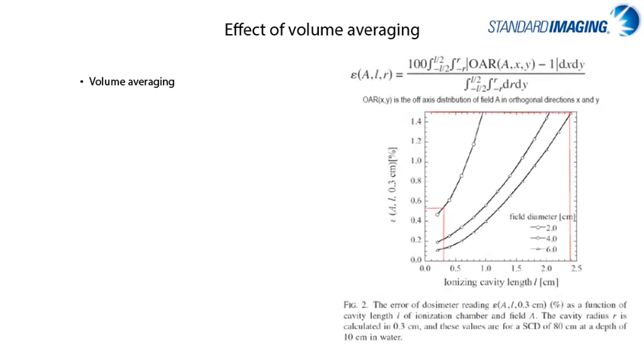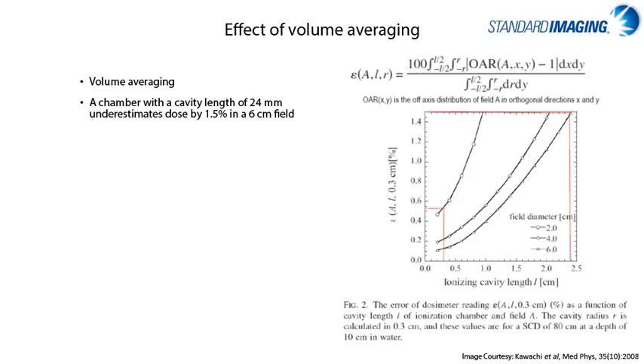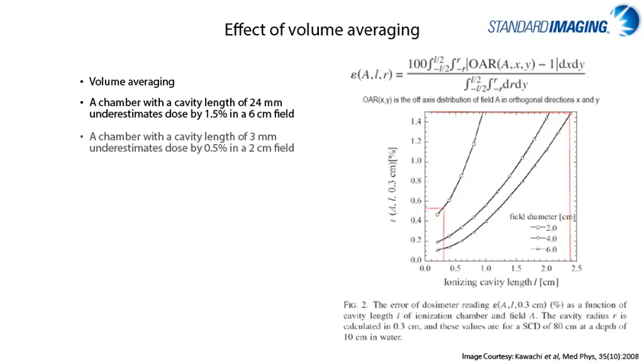An example, looking at this graph on the right from Kawachi and others, they looked at determining the off-axis ratios in a CyberKnife system for which the dose plateau region is very limited, and an approximate 1.5% error in readings can exist if a 24mm length chamber was utilized in a 6cm field. And further, a 0.5% underestimation in readings is observed when using a chamber with a cavity length of 3mm in a 2cm field according to this study.